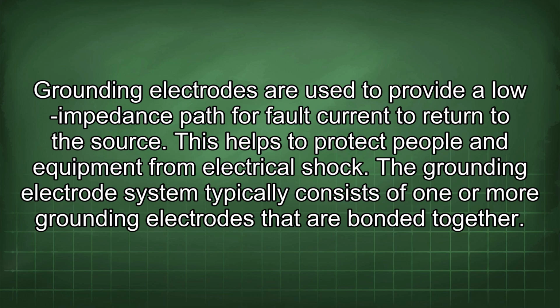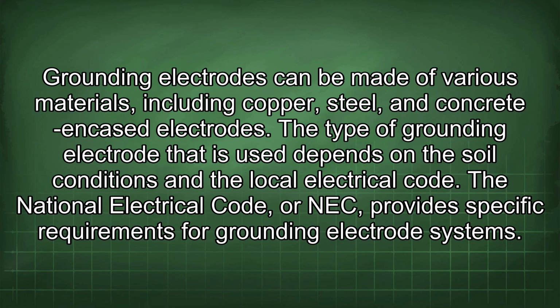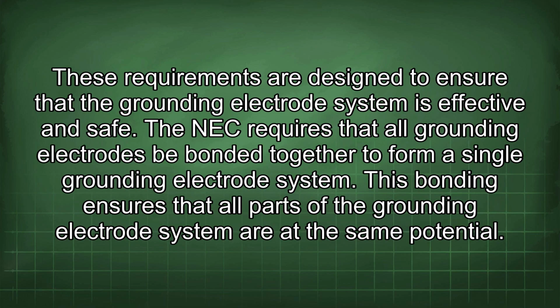The grounding electrode system typically consists of one or more grounding electrodes that are bonded together. Grounding electrodes can be made of various materials, including copper, steel, and concrete encased electrodes. The type of grounding electrode that is used depends on the soil conditions and the local electrical code. The National Electrical Code, or NEC, provides specific requirements for grounding electrode systems. These requirements are designed to ensure that the grounding electrode system is effective and safe.